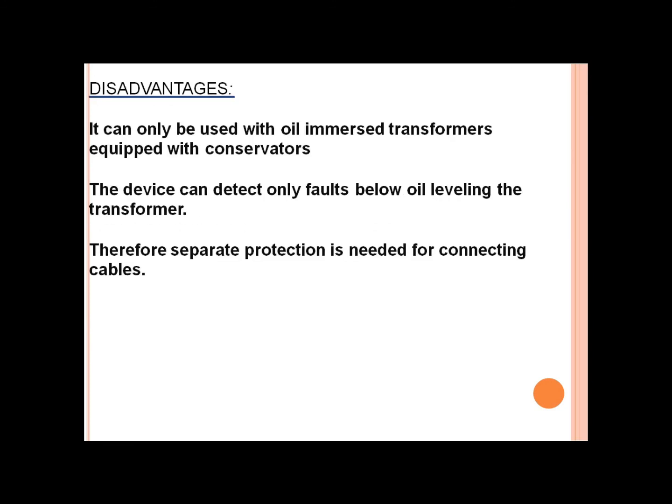Disadvantages: It can only be used with oil-immersed transformers equipped with conservators. The device can detect only faults below oil level in the transformer. Therefore, separate protection is needed for connecting cables. The main disadvantage is that the fault will only be detected when the oil is present. Besides, if there are cable faults or other faults, they cannot detect that fault.